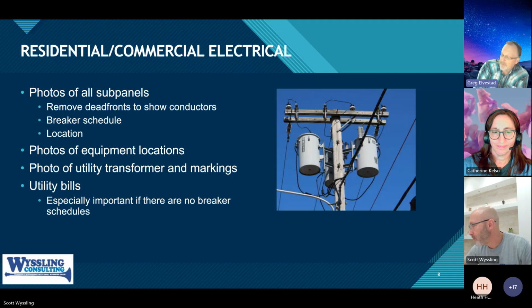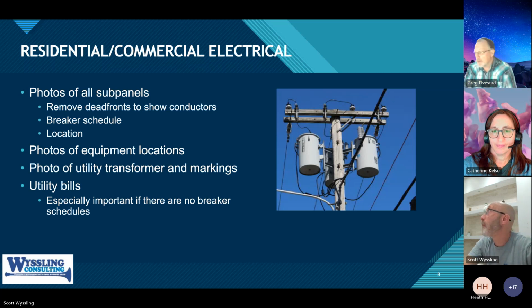It's just not going to happen, because we didn't invest that kind of money to have it sit there only to be utilized less than 25% of the time at its full capacity. So most of the time, the service transformer is likely to be half the service entrance rating. Could even be smaller, so be aware of that as you're looking at these.